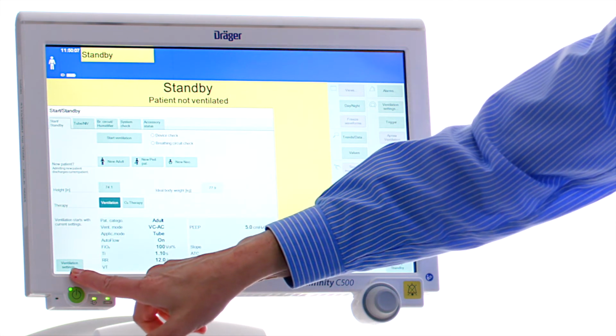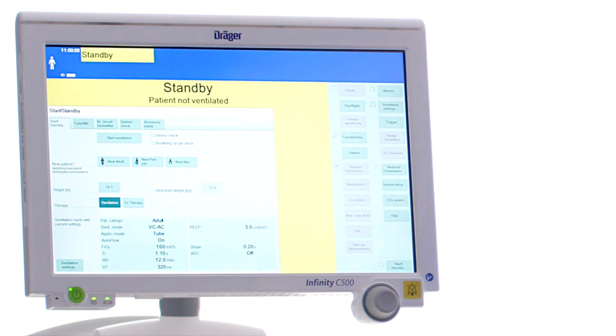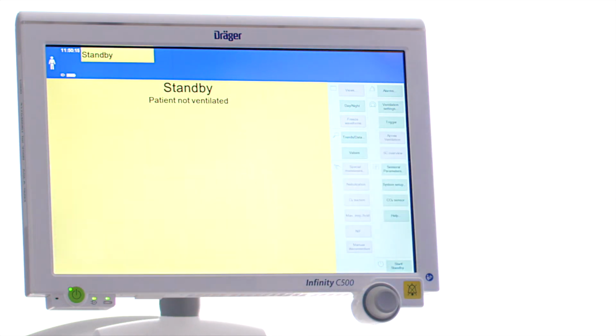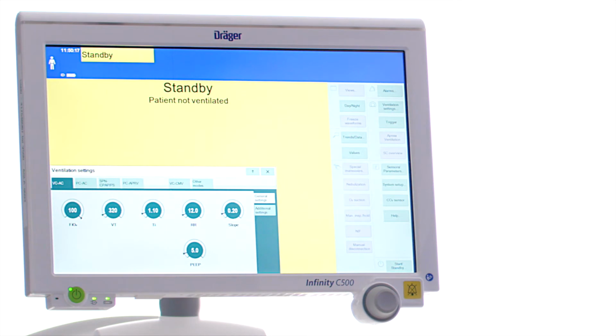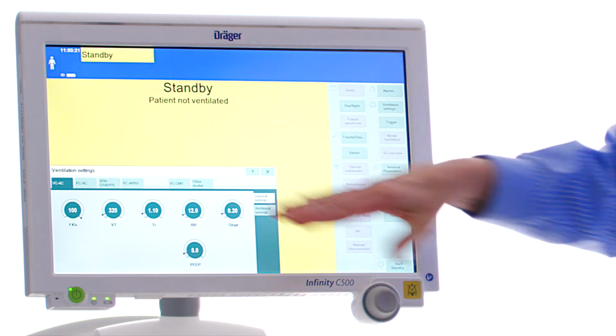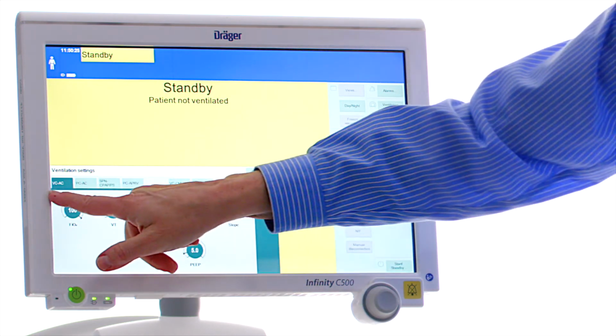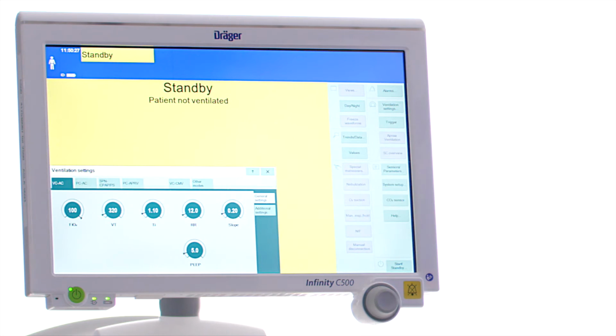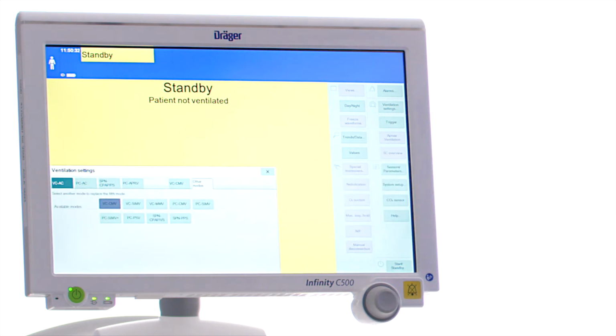In the lower left-hand corner of the screen, you're going to see the button that says Ventilation Settings. This is where we go to set all of our parameters. Touch the Ventilation Settings tab, and it will open the Ventilation Settings window. In this window, you're going to see the modes of ventilation across the top. The first 4 modes are configurable to the modes that are used most often. Other modes shows you all of the modes that the ventilator has.